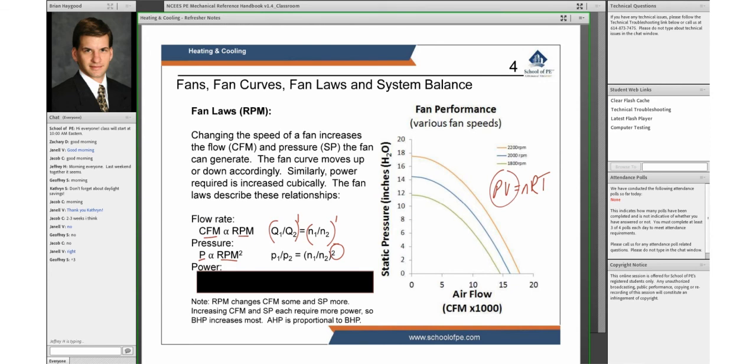What we're talking about here is volumetric flow rate in CFM, which is V dot, times pressure to get power. So since power is PV dot, if the P pressure takes an exponent of 2 and the V dot takes an exponent of 1, the power varies with an exponent of 3.